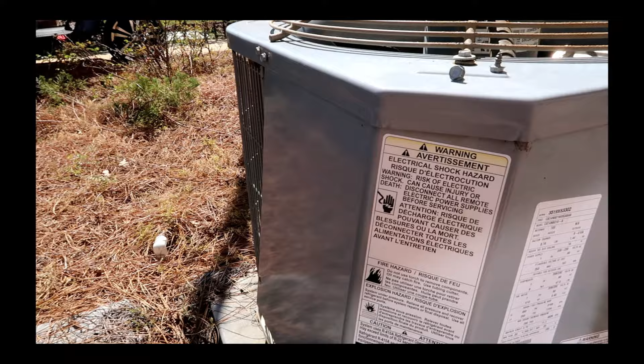Yep, they got the yellow on Herm and blue on the common. These go the other way. That's the culprit, that's why the fan was turning the wrong way. What a dramatic unit, this thing's just had me all blowed up today on a Friday too. So blue is Herm on the carrier condensers, and yellow is the common.